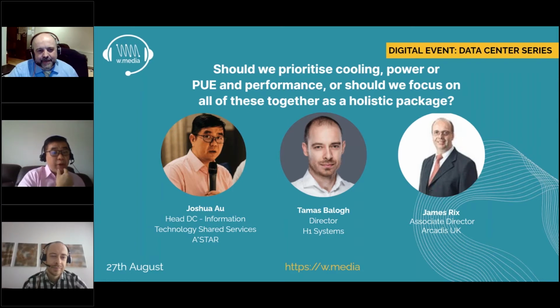PUE was a great idea when it was introduced some years back. Since then, PUE has mobilized sentiments for enterprises - it has helped shape the narrative. Having said that, if we refer to the first white paper published by the Green Grid, all the way to the latest one published by the Green Grid but authored by Future Facilities - likely written by Mark Seymour himself - they highlight that PUE should be seen as a trade-off, and must be considered holistically with other factors as well.